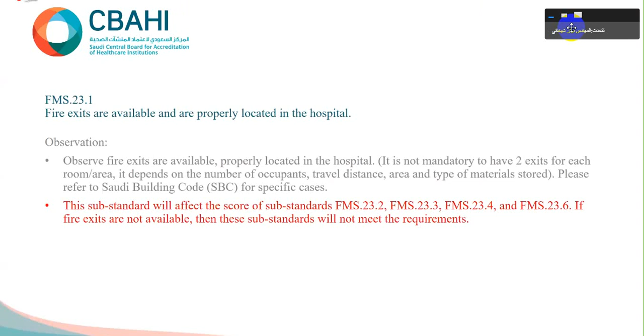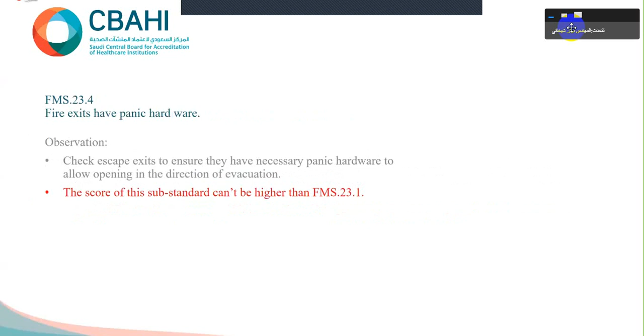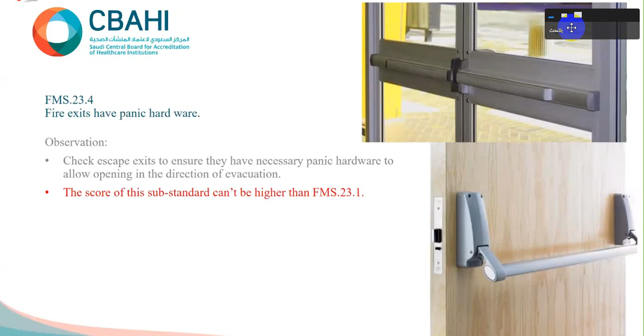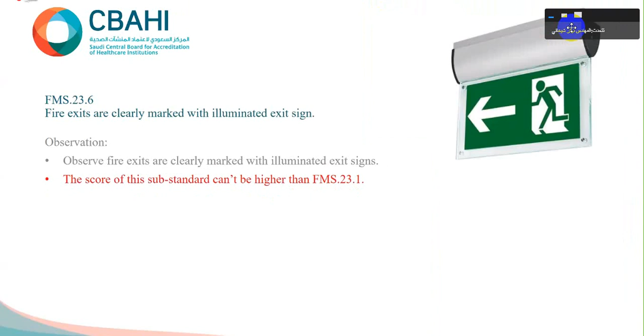23, talking about fire exits, and here I know we will have a lot of questions. Let me tell you something. All fire doors are emergency exits, but not all emergency exits are fire doors. So we have two kinds of doors. Exit doors should not be fire rated, while the doors between two fire zones should be fire rated. Fire exits should not be locked. We should have panic hardware in the direction of the escape, but for the outdoor, a fire exit open to air is not required to be fire rated or even have panic hardware. We should have the fire exit clearly marked, illuminated, and connected to the generator.